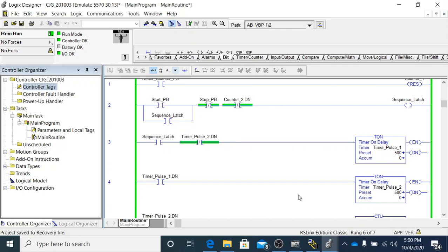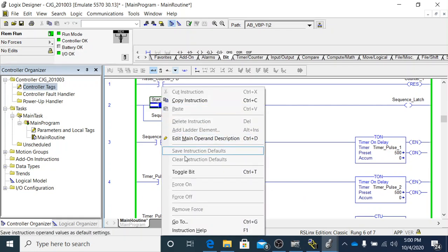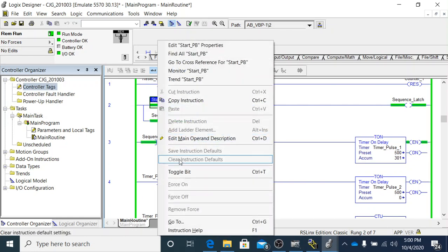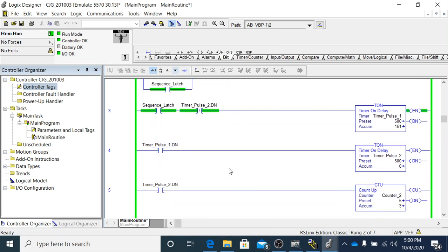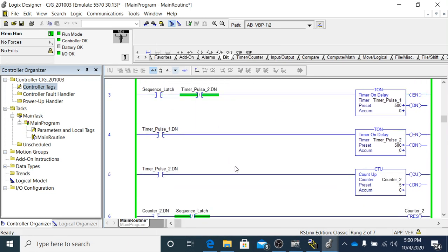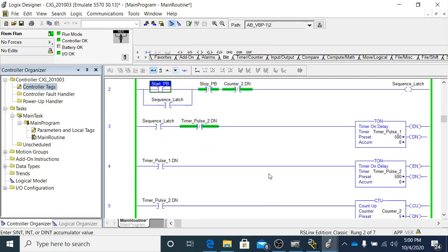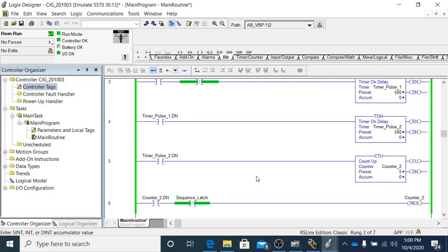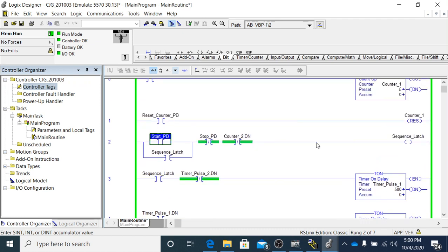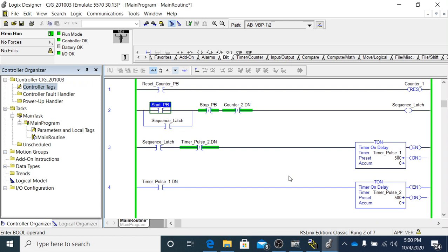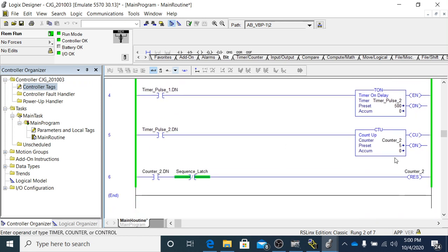and that's why I wanted to show you this, is I want to show it to you again. We're going to toggle to start the sequence. We're going to toggle it back off. It's sitting here pulsing, and it's counting. Then we go to 5, it unlatches, and then after it unlatches, so the counter has to be done, all right, and the sequence latch has to be unlatched. Then we'll reset to 0. So that way it's ready for the next one.